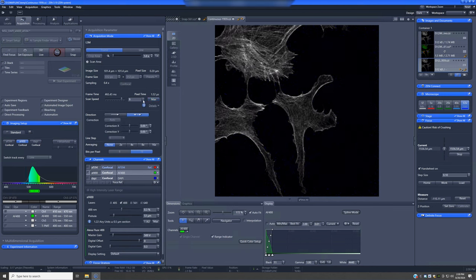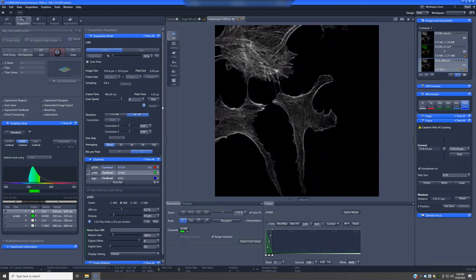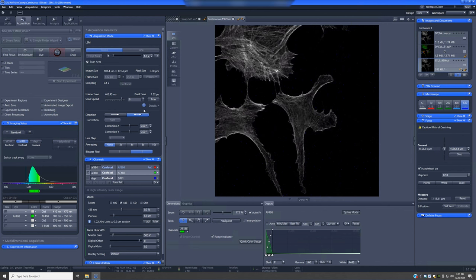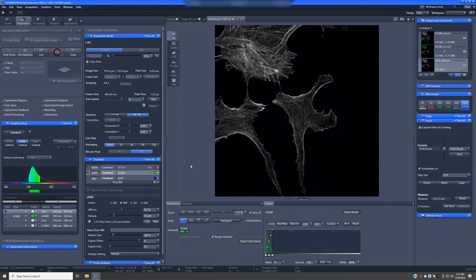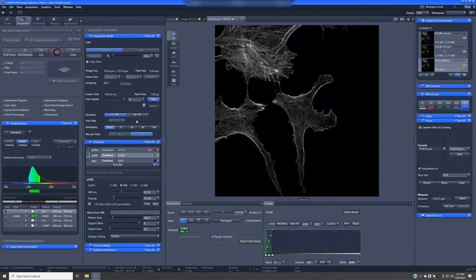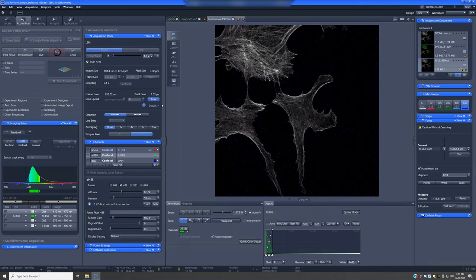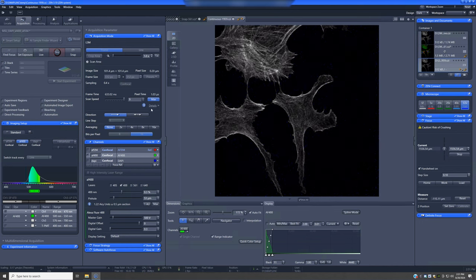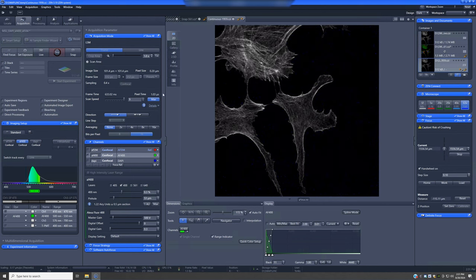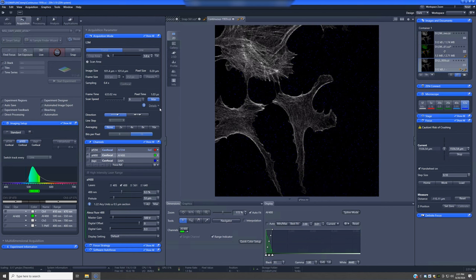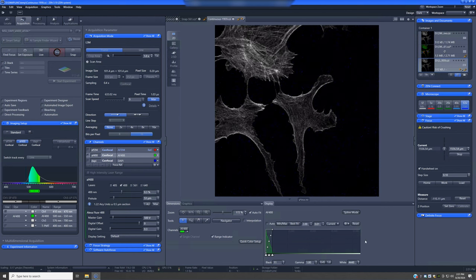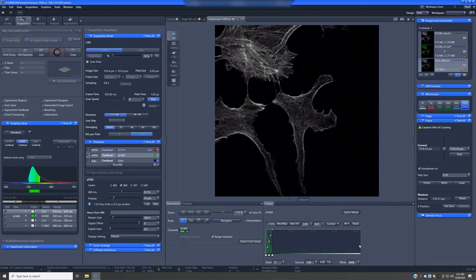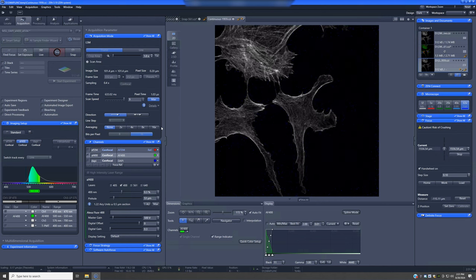So if you have that scenario, if you lower the speed a little bit, you can see we went from one microsecond pixel dwell time on each pixel to 1.5, that's not as much of a time investment as going from unidirectional to bidirectional. But lowering the speed by that much can sometimes improve the quality, and so you're still faster than doing unidirectional at maximum speed. Outside of those scenarios, I really don't recommend you change the scan speed. I would leave it at the maximum. The only exceptions are if you've maxed out the laser, maxed out the averaging, and still want more quality. If you're in that situation with a typical biological sample, that usually means there's something wrong with your sample. For chemical samples, sometimes that is useful, but for biological samples, if you have to lower the scan speed, that indicates a problem more than anything else.